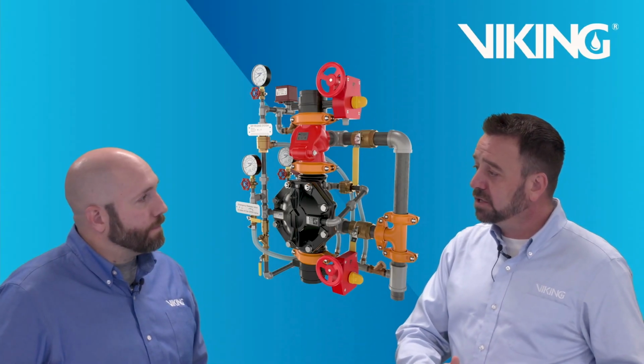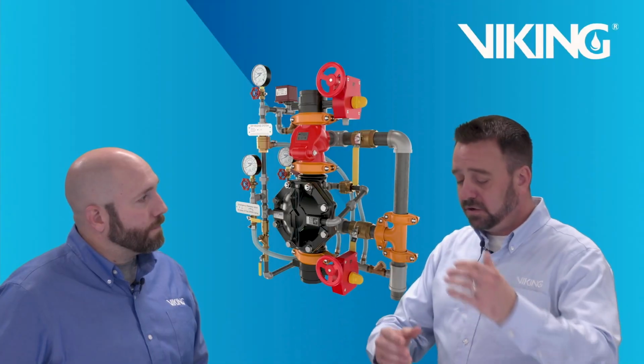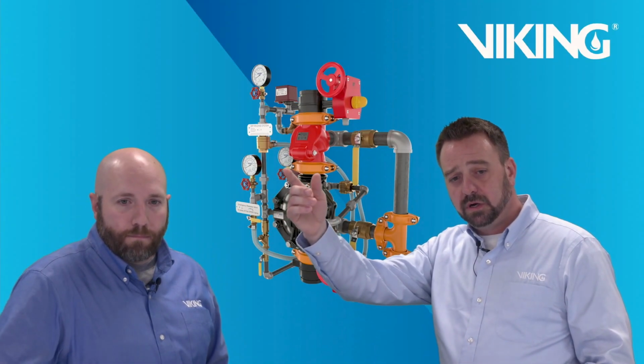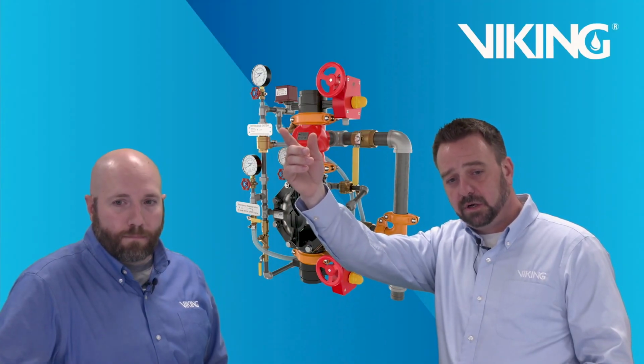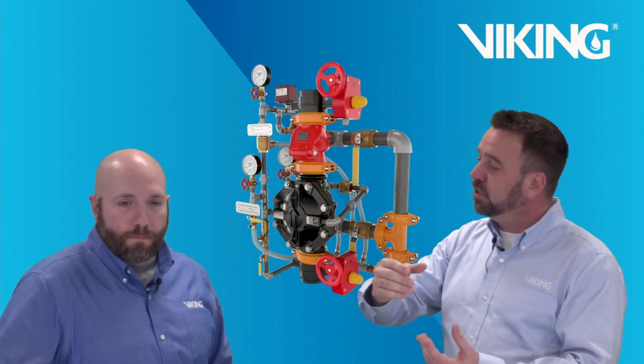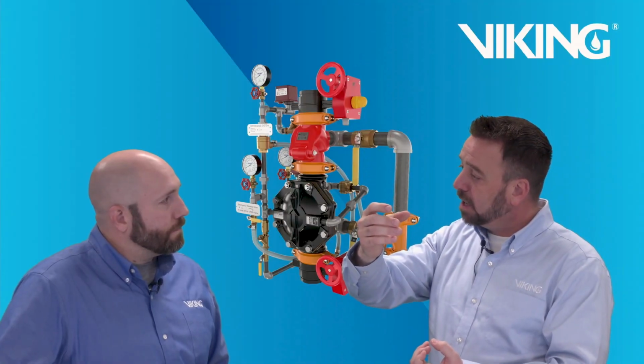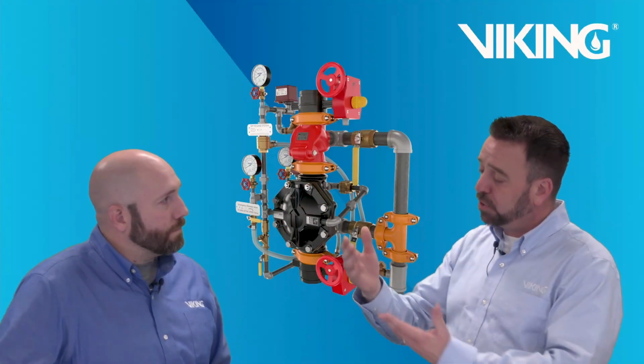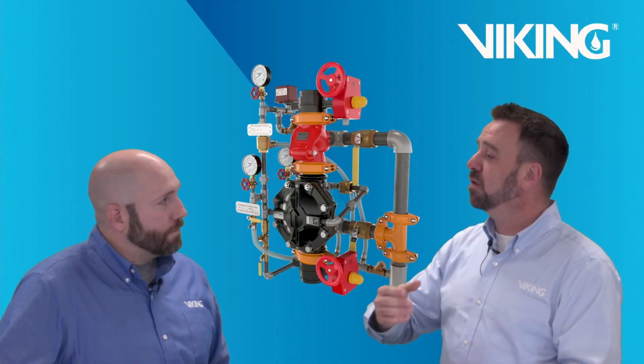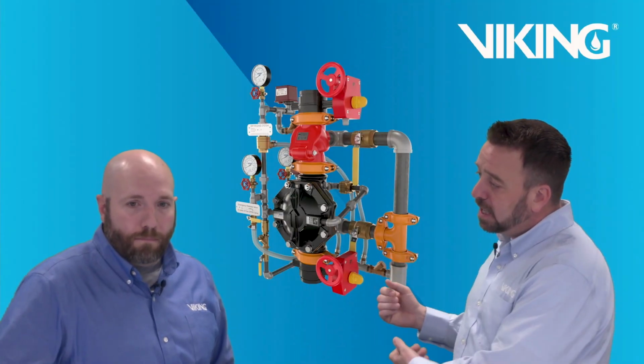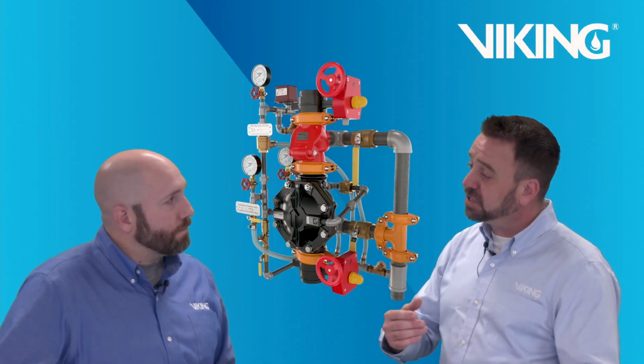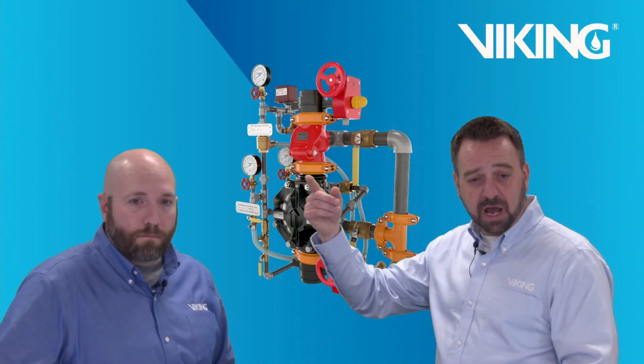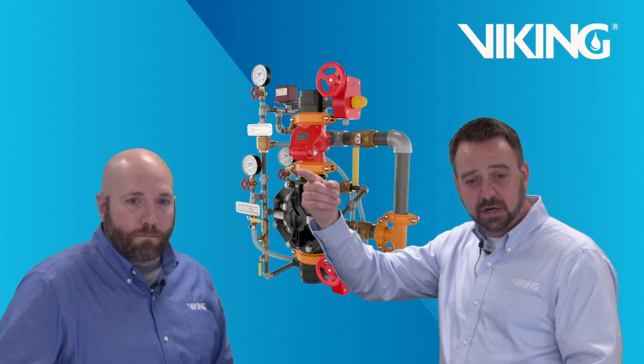Okay. And a nice thing about the dry to pre-action upgradable system is that you can just remove, you can see there we got a union below and a union above the A1 differential valve. And if you just loosen those unions, when a tenant moves in to upgrade to a pre-action system, you would remove that A1 differential valve at the unions, and then we offer kits to upgrade to a single interlock or a double interlock pre-action system that are just going to fit right back in here at the unions above and below.